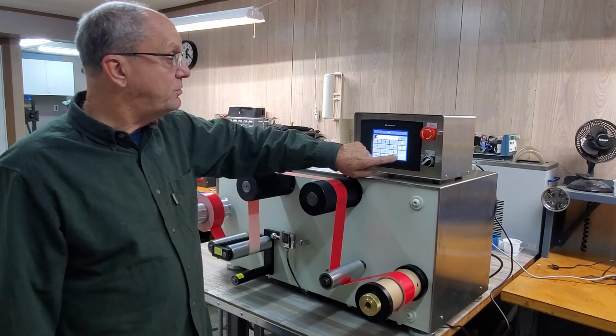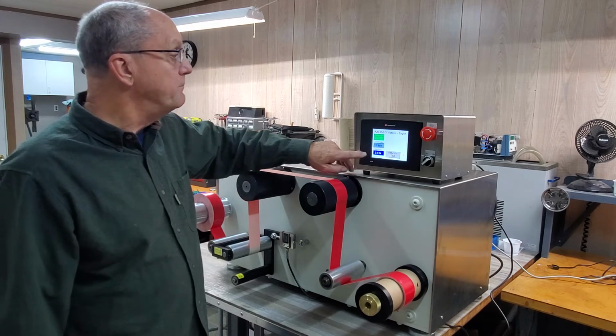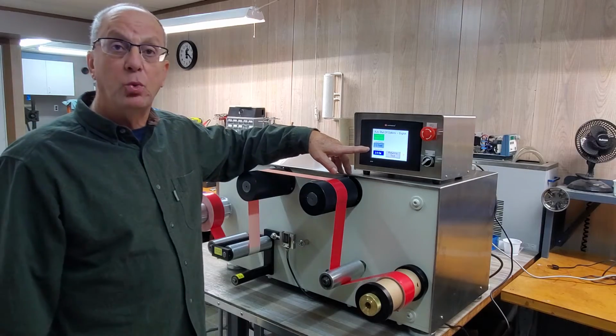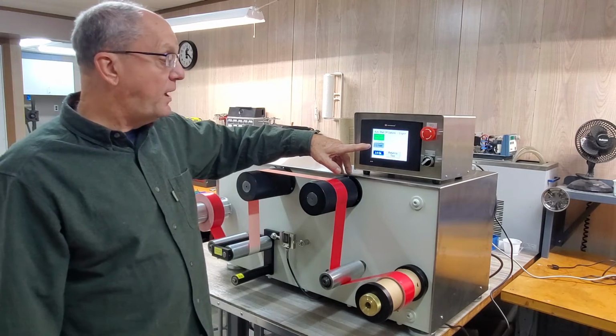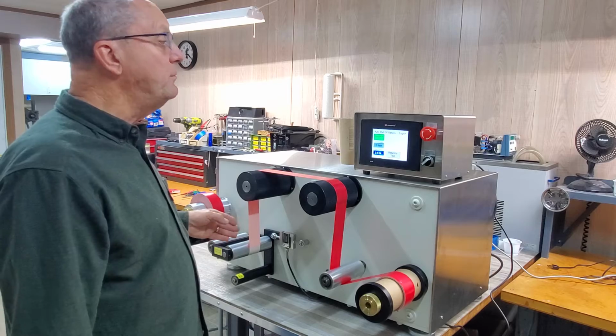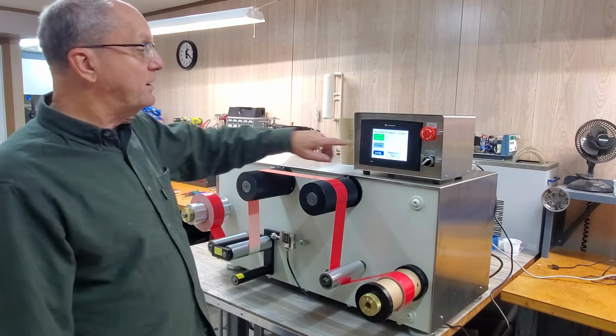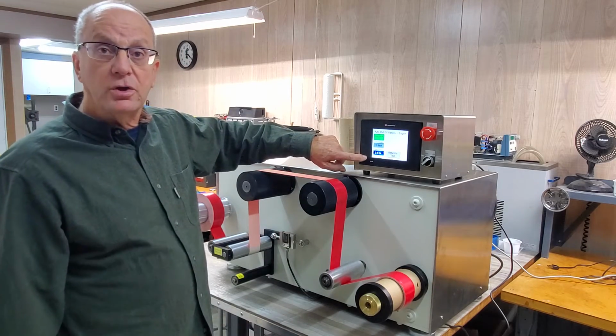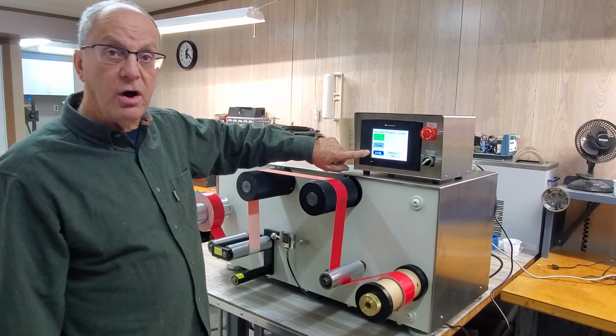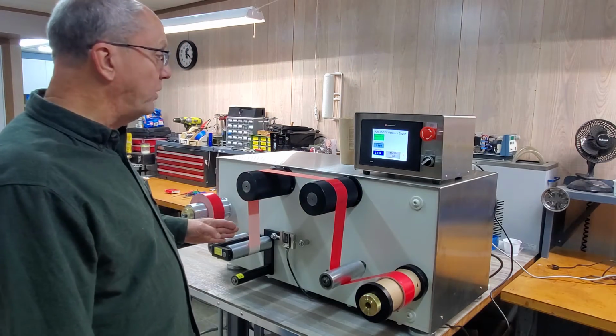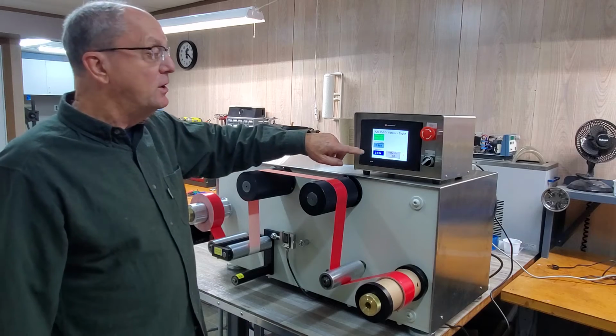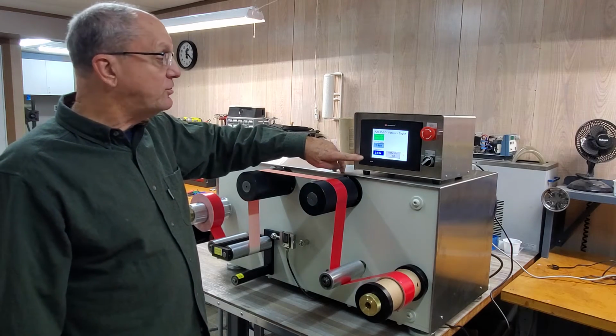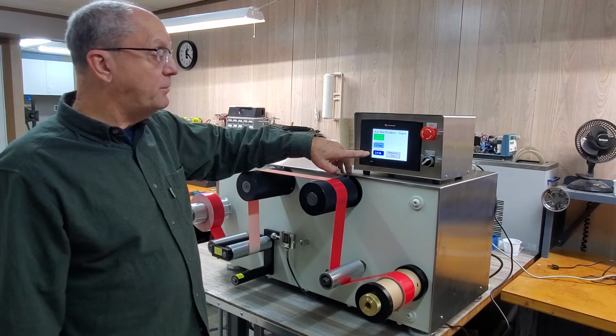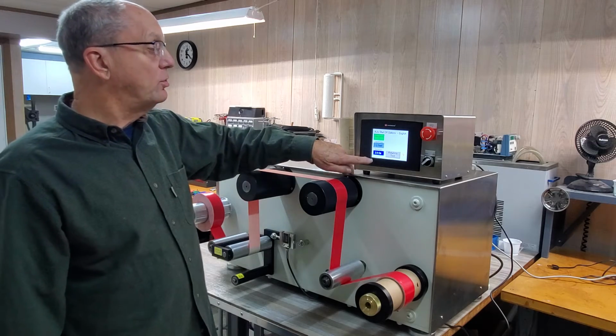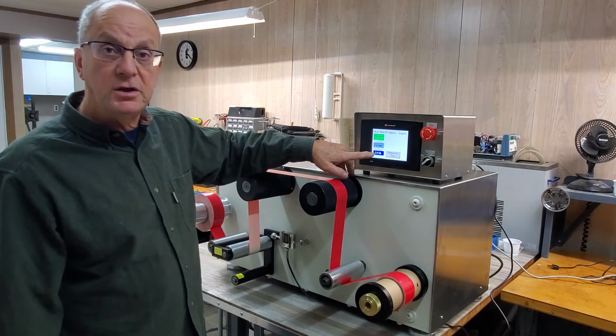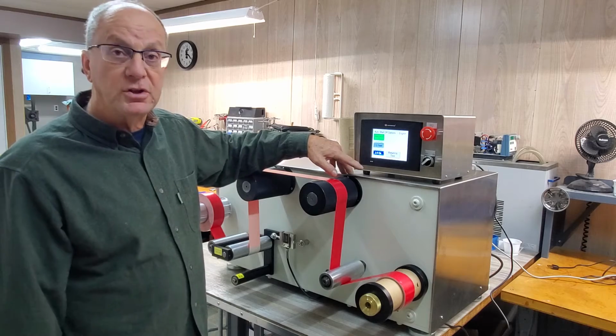All of these numbers can be changed simply by touching the display. But I have my shut off inhibit set to 1 foot. What that means is that we're going to let at least 1 foot of material pay out of this thing before we start looking at that tension value to shut it off. So that's going to let us have 1 foot of material to get the slack out so that we can run a meaningful test. And then at that point, when the tension goes under 2 ounces, as I have keyed in here now, it's going to shut off the test.